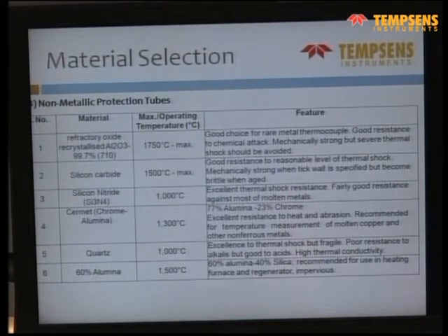Then coming to non-metallic, there are various kinds of non-metallic protection tubes which are available. The first one is the most common, which is called alumina. This is 99.7% alumina, or it is also called C799 or 710 tube. It has 99.7% alumina and is suitable up to 1750 degrees centigrade. And this is the most common tube which is used for all platinum thermocouples. So for all R-type, S-type, B-type thermocouples, this is the primary tube which is used. Even in combination with any other tube, the inner tube has to be this alumina tube.